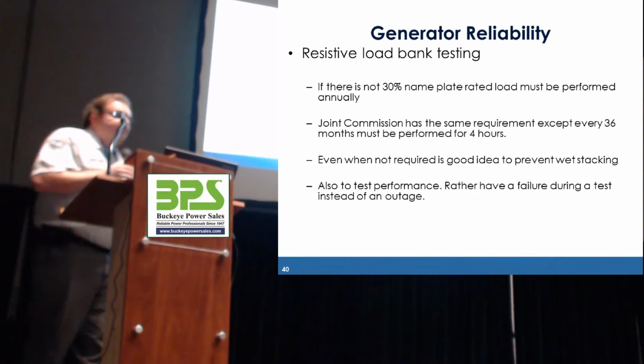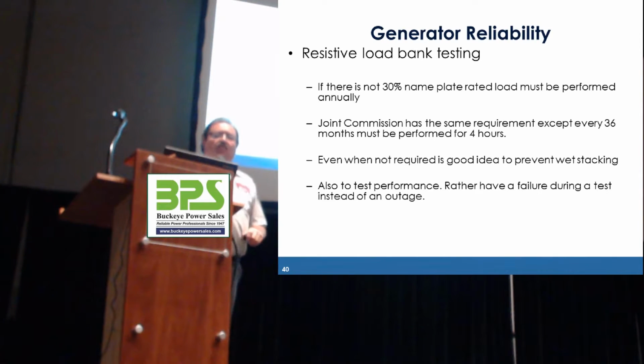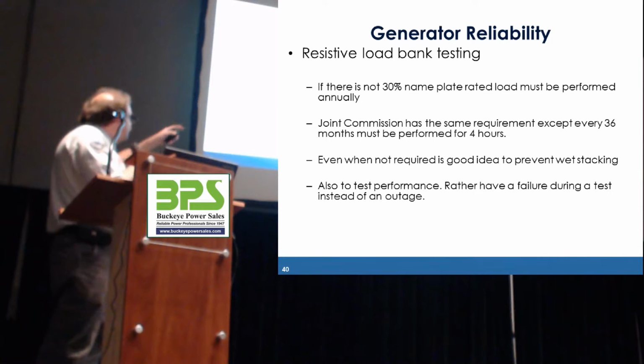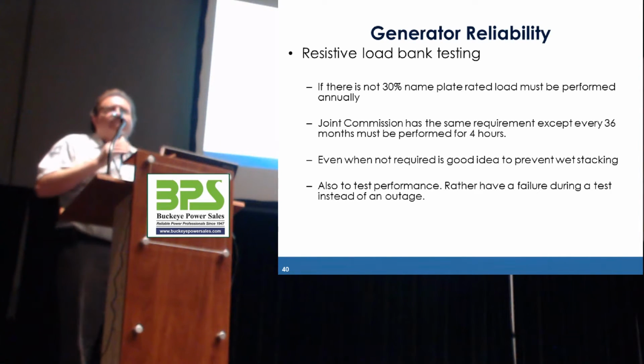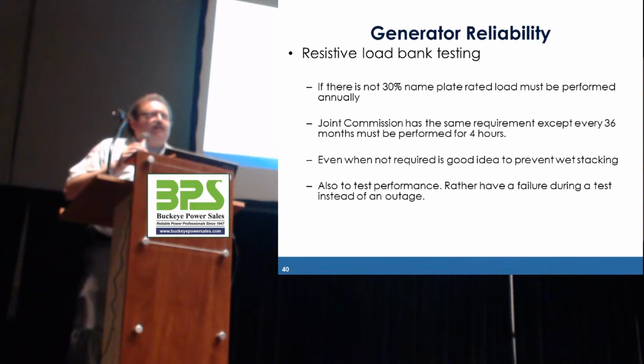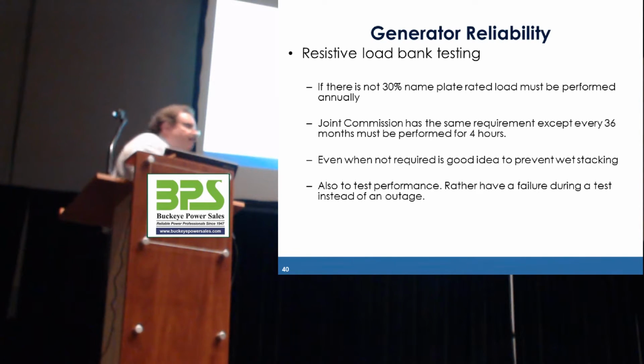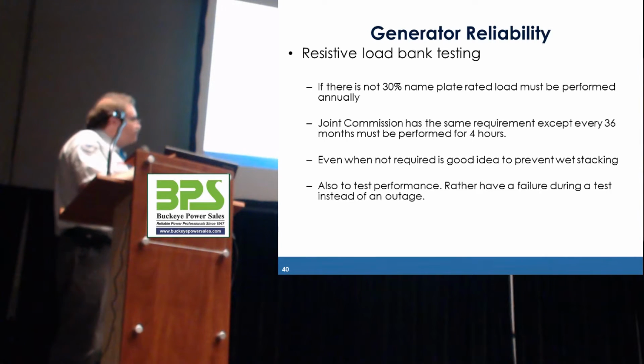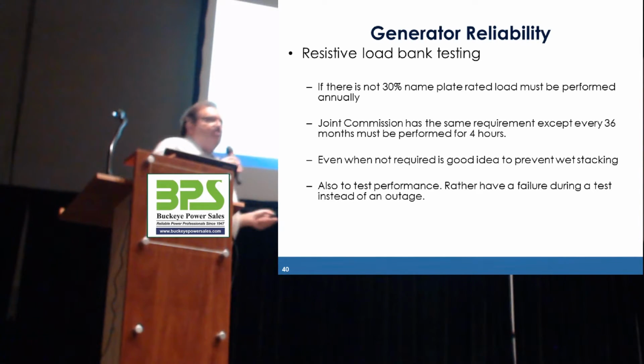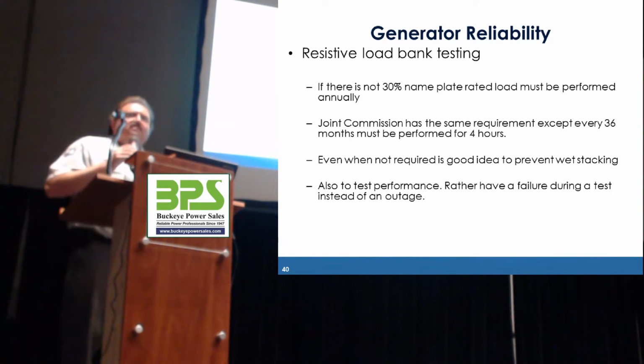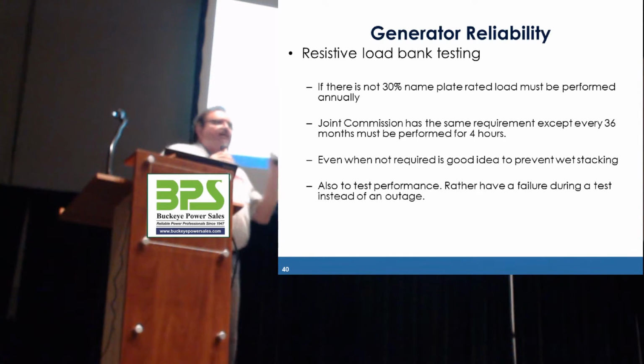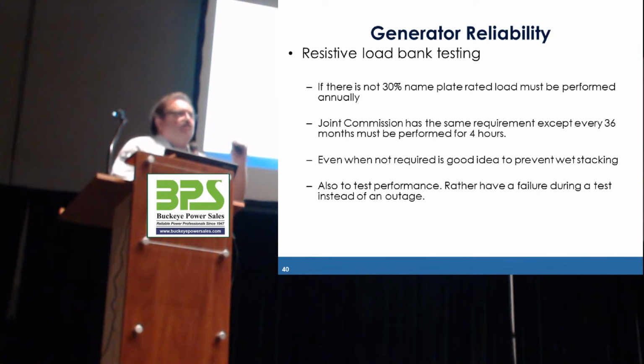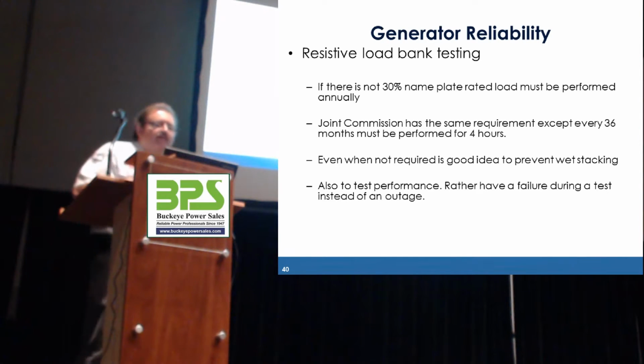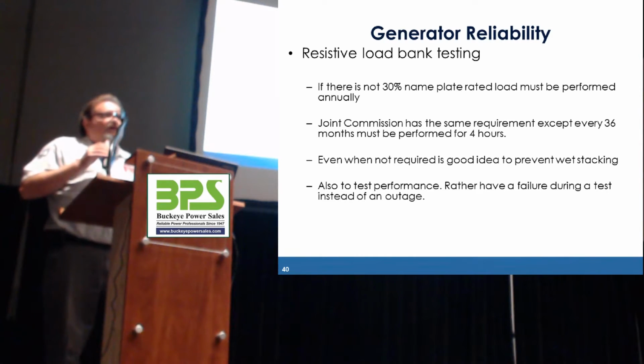The load bank testing that we talked about is done by using a resistive load bank, runs it up to 100% or 75% or whatever you choose it to be, because this isn't life safety. You need to run it to at least 75%. If it were a life safety, it says we have to run it to 75% once a year. If it's Joint Commission, which is the people who oversee hospitals, then once every 3 years it has to be done for 4 hours, and the second 2 hours has to be at 100%. So the more load you can put on that machine, the better that it's going to be. Even, like we said, even when it's not wet stacking.